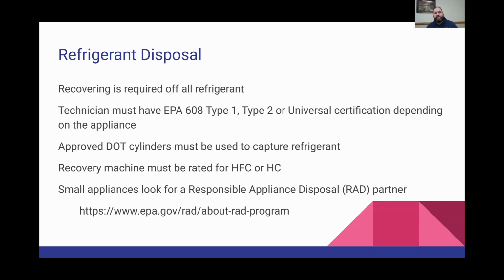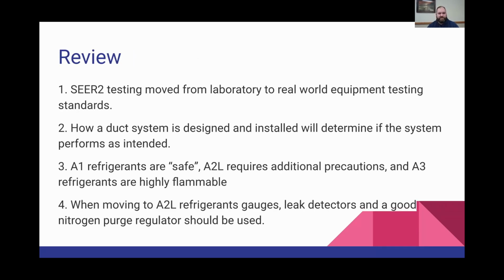Your recovery machine, I mentioned this before, needs to be rated for whatever you're removing. A machine that's rated for hydrocarbons can also be used for HFCs, but one that's good for HFCs may not be approved for hydrocarbons. And then lastly, if you're getting rid of small appliances, the EPA does run a program called the Responsible Appliance Disposal Program, and contractors and utilities and other groups can sign up to be partners in that. So if you're looking to get rid of stuff, and somebody shows up with a broken down truck and says, I'll get rid of it for you, likely they're not a responsible appliance disposal partner. So just keep that in the back of your mind. Look for an approved way to dispose of it.